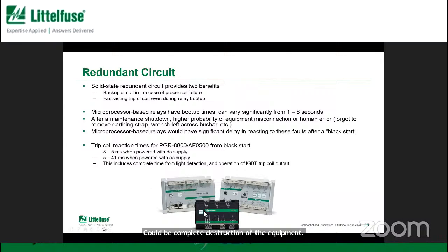So with these arc flash relays, with the Littelfuse relays, that redundant circuit is able to react extremely fast because it does not require a microprocessor to boot up. So we can have a trip signal if you're powering the product with a DC power supply. We can still issue a trip within 5 milliseconds right from a dead start. So that is also a very nice safety feature.